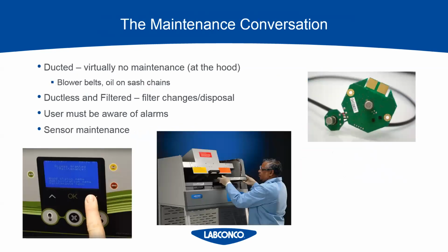The maintenance conversation is always an important one with any type of carbon filtered hood, because the maintenance is inevitable on these hoods. People are mostly used to working with ducted hoods, where they may never have to touch anything in order to work with the hood. They're all pretty much set it and forget it. But on a ductless hood, there will be alarms that are not typical on a ducted fume hood. So the lab personnel need to be properly trained on what to do in the event of that alarm. And someone at the facility or a pre-planned third-party company needs to be able to service that hood and perform filter changes. And then even on a DH3 hood, there's an acid sensor change out that needs to be done every 2 years. So there is much more maintenance than what is involved on a ducted hood.